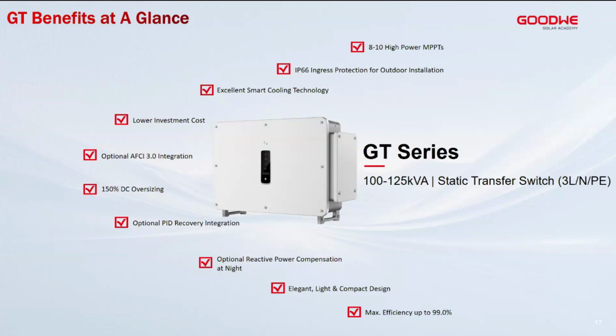Now, the purchase cost of these products has been reduced, so it's now more affordable for the C&I sector. For example, the 100 kilowatt is now more compact, with fewer ports and fewer MPPTs, and it's now more affordable but still of high power. Uniquely, in case you'd like to integrate the arc-fault circuit interrupter, the GT series comes with the 3.0 version of the AFCI, to increase the sensitivity and the fast response to prevent any arcs on your PV strings.